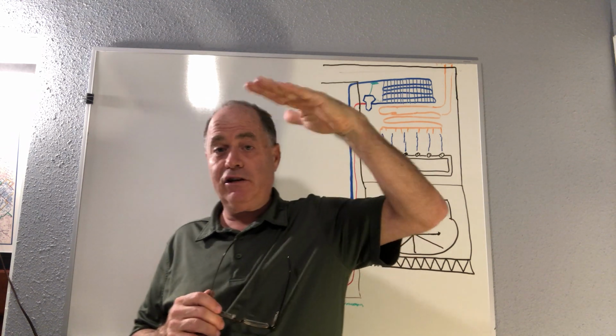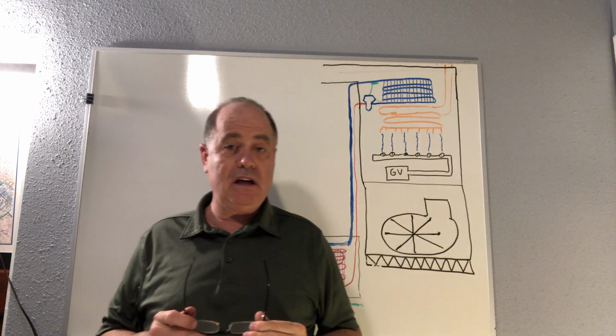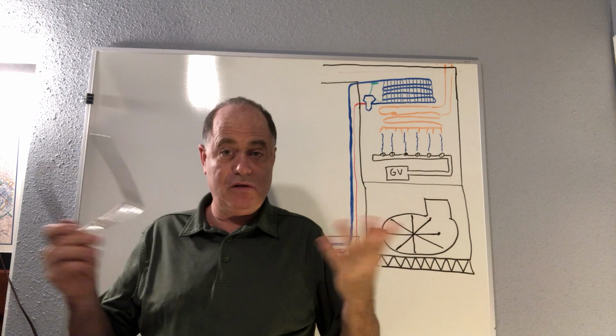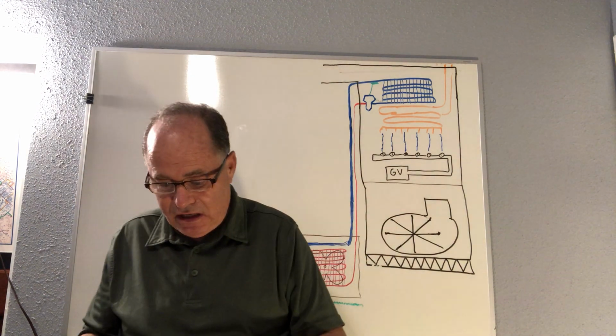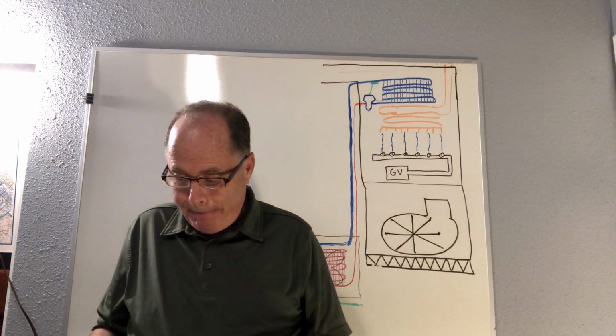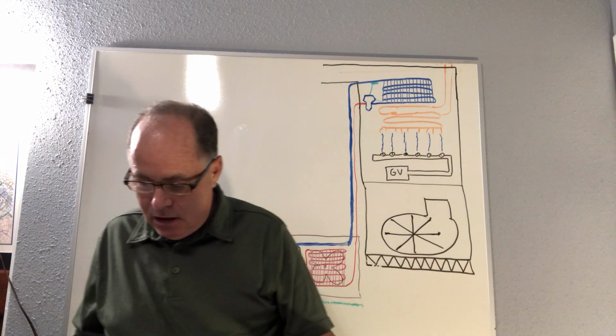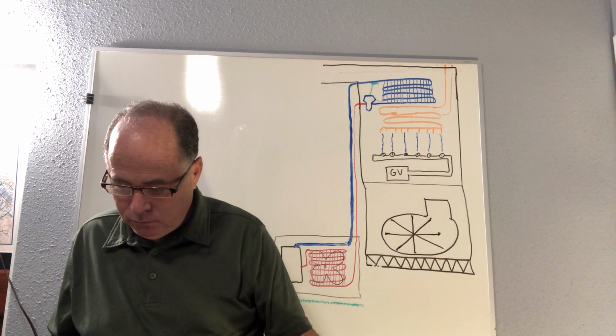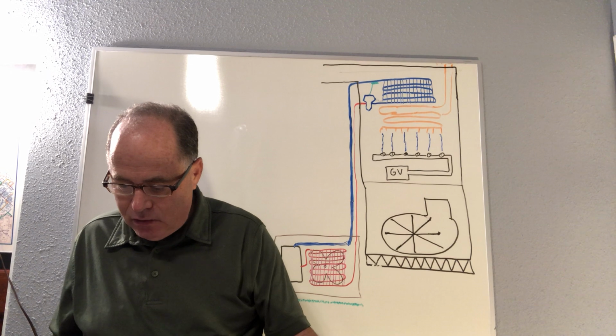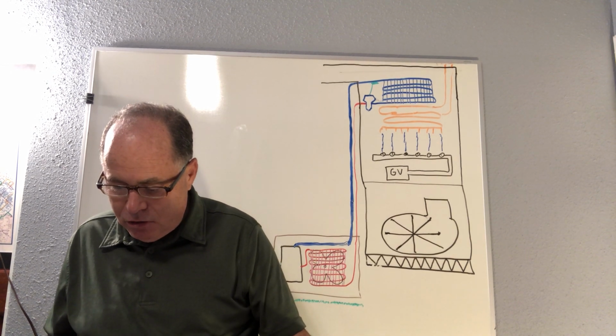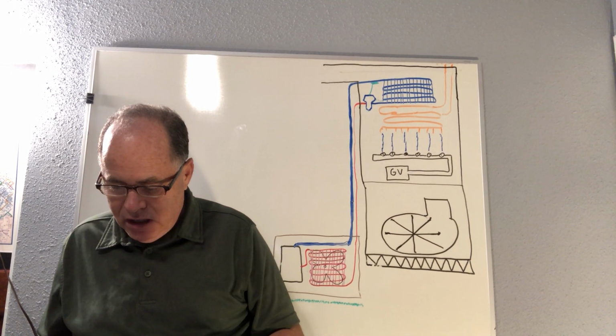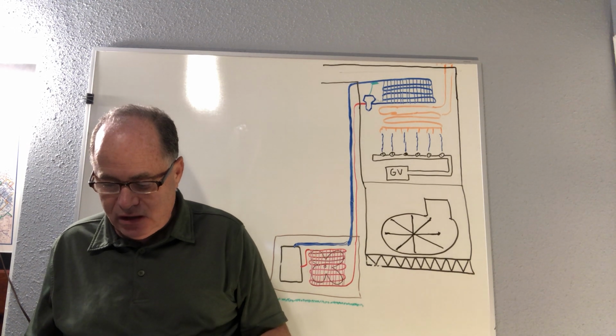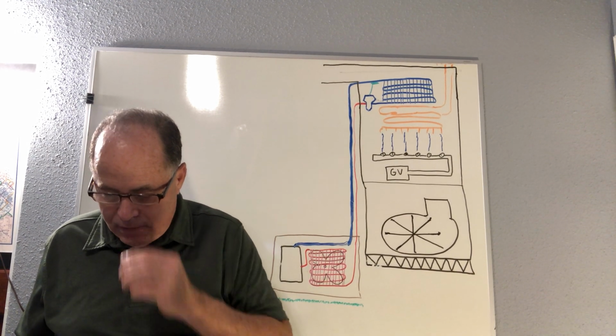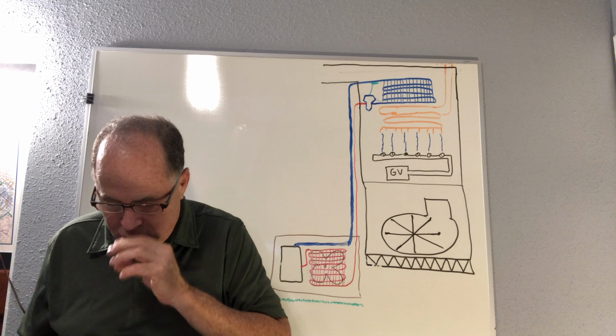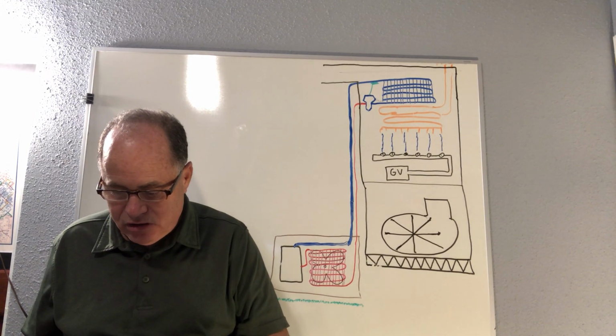you have to have proper clearance over your cooking things by code, so that you won't have fires and things of this nature. Okay. Then to finish up, here it talks about factory-built commercial incinerators and crematories shall comply with UL 2790 and installed in accordance with the manufacturer's installation instructions.